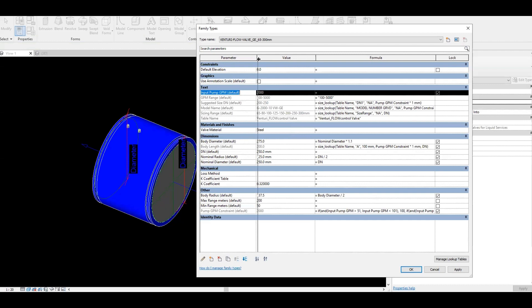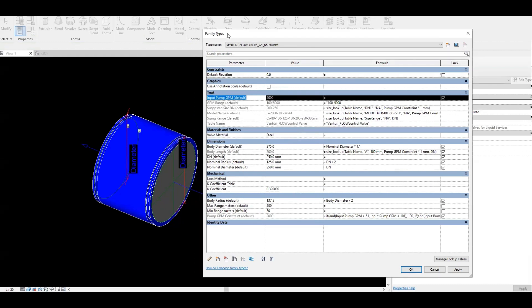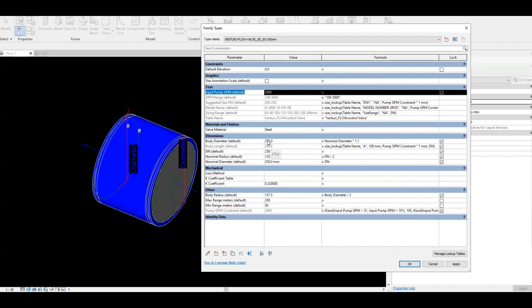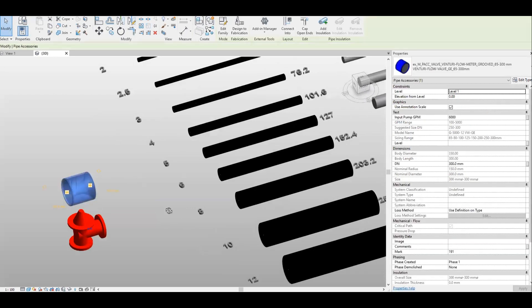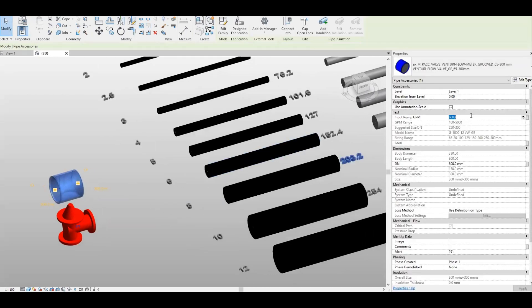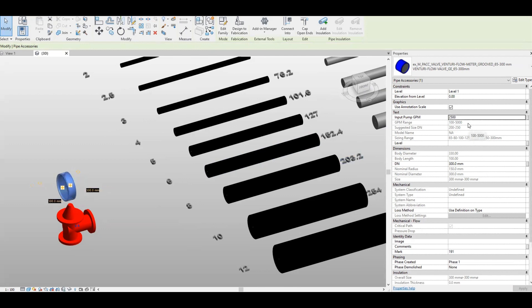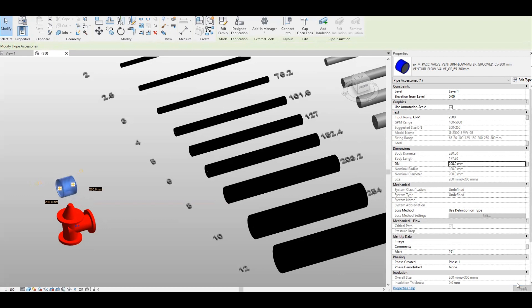I'll show you now the actual process of using this valve. We'll close this and go back to the project. Let's say your pump capacity in GPM is 2,000 or 2,500. When you select that and apply — for 2,500, the suggested size will be 200 to 250. As you can see, the DN here is already out of range at 300 millimeter, so you lower it to 200 to 250. Let's say we select 200, and it will now go to the correct size.